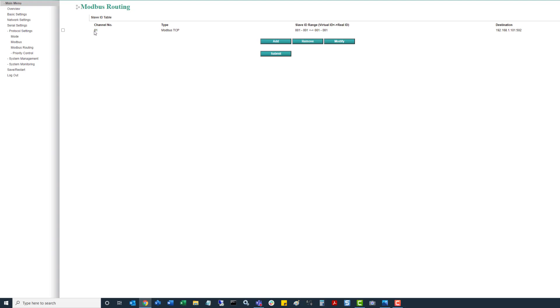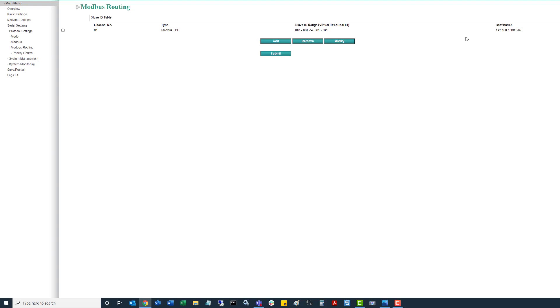So now we can see channel 1. It's doing Modbus TCP on that output, acting as a master. And we can see when a request comes in to this master unit for slave ID 1, it's going to be looking for slave ID 1 based on this IP address. So if all the field controllers are using slave ID 1, you don't need to go through and reprogram them. This is one of the slick features that Moxa has incorporated.